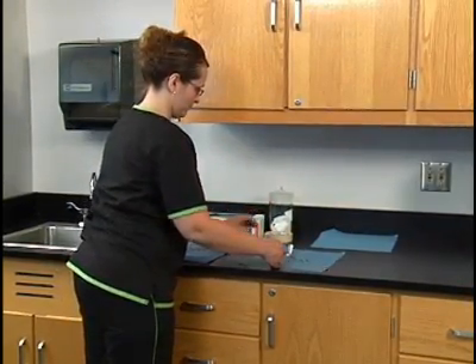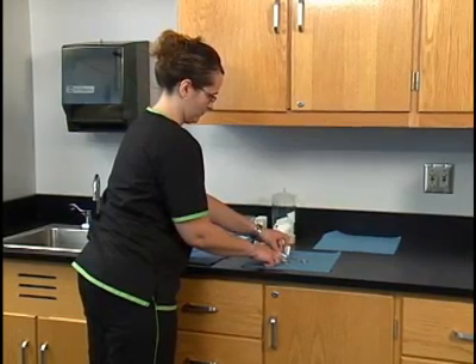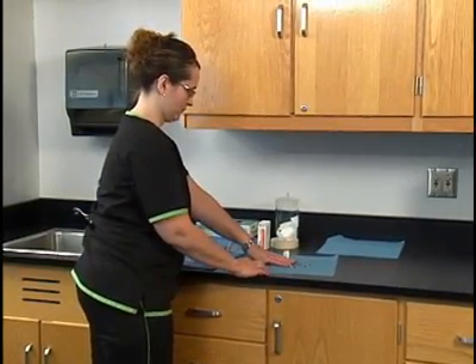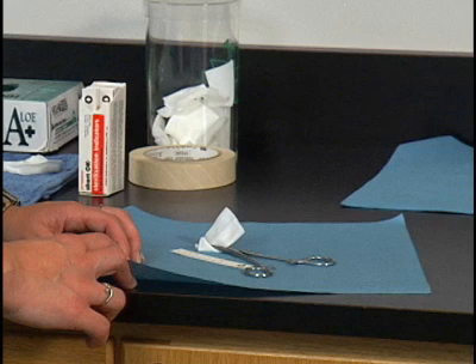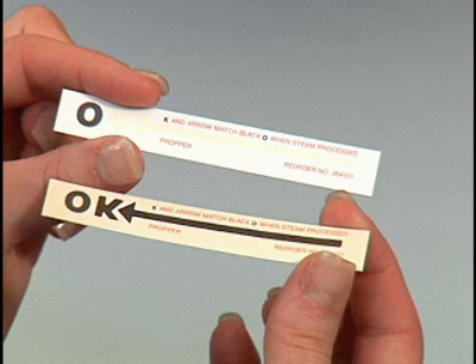Place a sterilization indicator in the center of the pack next to the instrument. When the pack is opened, the sterilization indicator will be changed in some way if the process was effective and the item is sterile. With this indicator, an O is stamped on the indicator. If the sterilization process is effective, a K appears next to the O to form the word OK, along with an arrow pointing to the word OK. If the sterilization indicator does not change appropriately, the item is not sterile and must not be used.